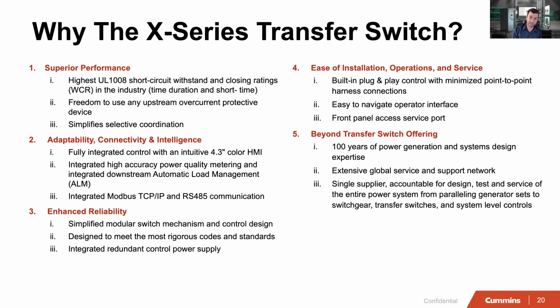Also, the control itself, the adaptability, connectivity, and intelligence. Fully integrated control with an intuitive 4.3 HMI color screen. It's packed with features with you in mind, such as the integrated high accuracy power quality metering, alerts, faults, and alarms, integrated Modbus communication, TCP/IP, and RS-485 for connecting to a SCADA system. The reliability, simplified modular mechanism with simplified control. It's designed and been tested to meet rigorous codes and standards, and it has enhanced reliability, say for data centers or mission critical where they require higher redundancy and reliability. There's an integrated power supply control for the transfer switch.